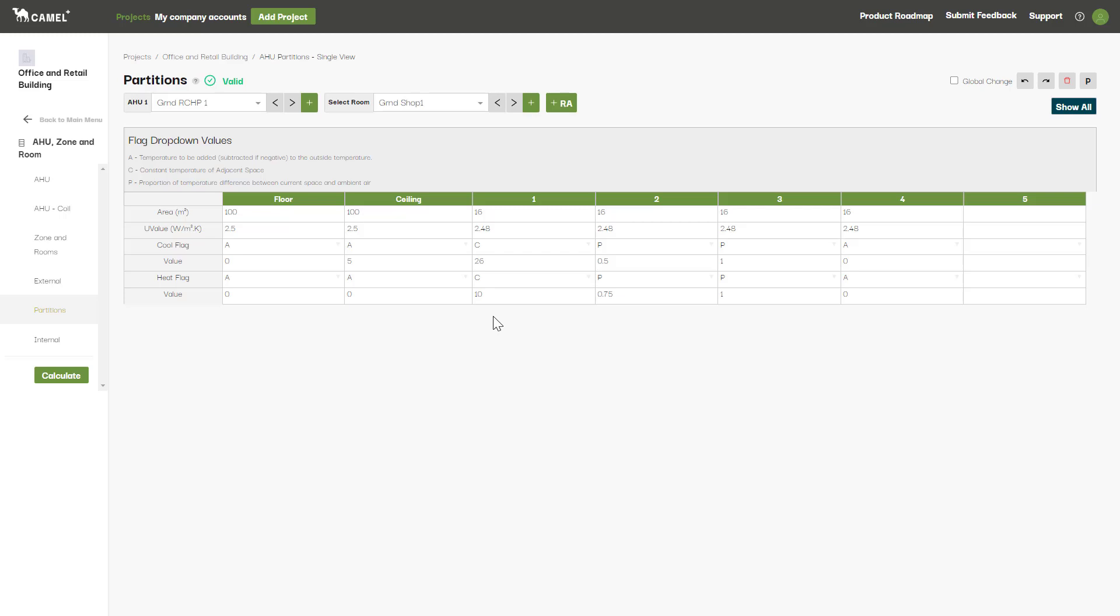CAMEL will use the difference between the adjacent space temperature and the internal design conditions specified for the room to find the delta T across the surface. This is then multiplied by the area and the U value entered here to find the heat transmission.